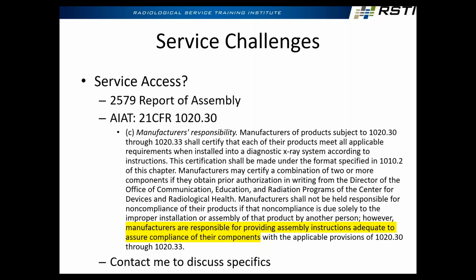Inverter, multiplier, collimator. So the FDA has a form. It's called Report of Assembly. It's a 2579 form. Anytime that anyone, third party, OEM, anyone changes a certified component, you're required to submit a 2579 form to the FDA. Okay. So each manufacturer has a list of certified components, but in summary, if it makes X-rays or is in the beam, it's a certified component. X-ray inverters, tubes, collimators, detectors, some tables.